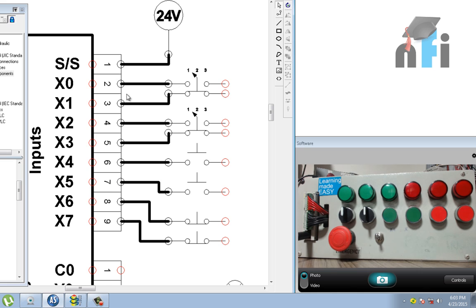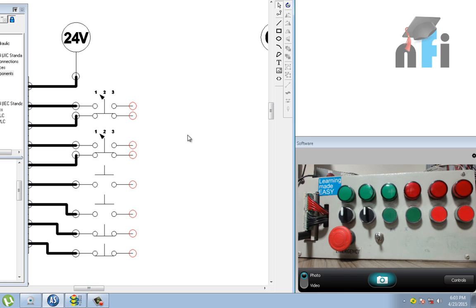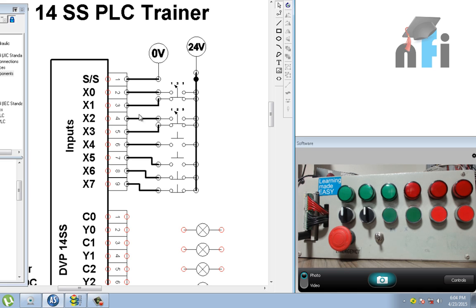One end of the input elements goes to the PLC input terminals. For the other end, following the sink source principle: since we connected 24V to the sink/source terminal, the other end of the switches is shorted and given 0V. Alternatively, you can connect 0V to the sink/source and 24V to the back of the inputs — both wiring methods work.